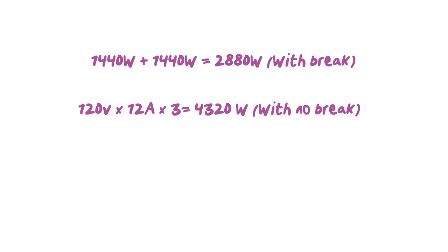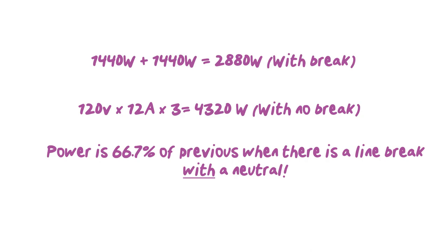And this is all leading up to a point here. It's leading up to the fact that power is always going to be 66.7% of the previous when there is a line break with a neutral. So again, power is always 66.7%. You don't have to go through and do all the crazy math. You can work out what your power was originally and take 66.7% of that, and then you'll end up with the power with a neutral break.